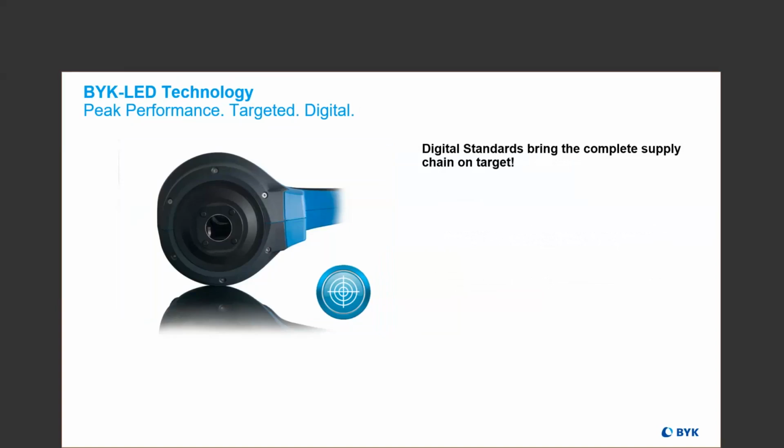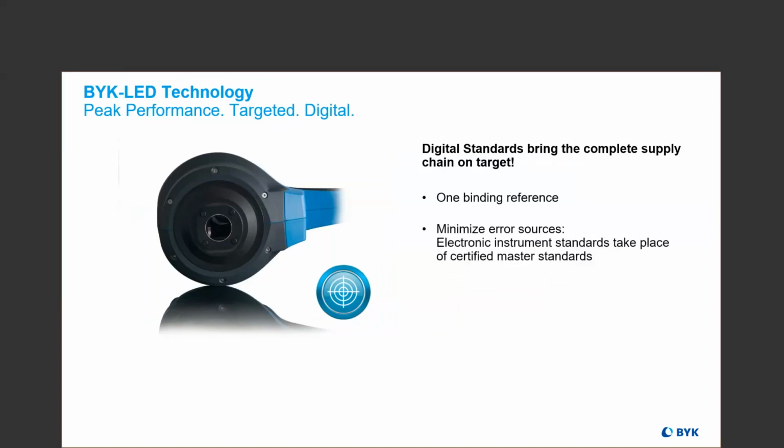This also allows for digital standards. Digital standards provide for one binding reference. This minimizes error sources because electronic or digital instrument standards take the place of certified master standards, and only instruments with excellent accuracy between instruments allow usage of digital standards.